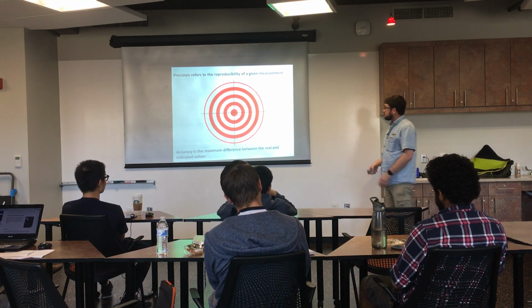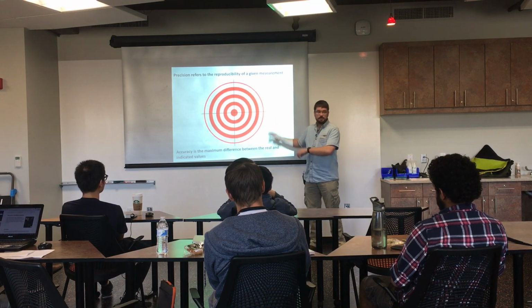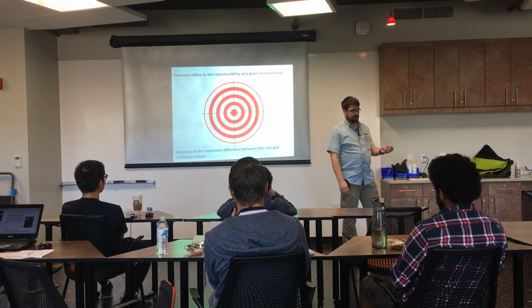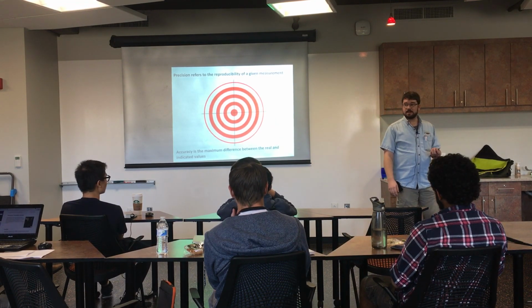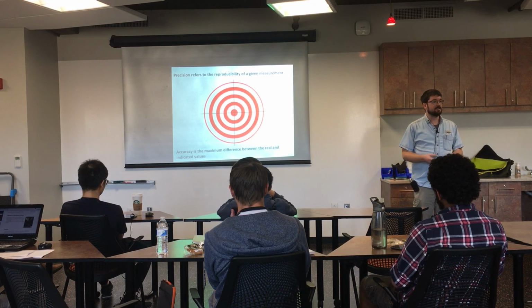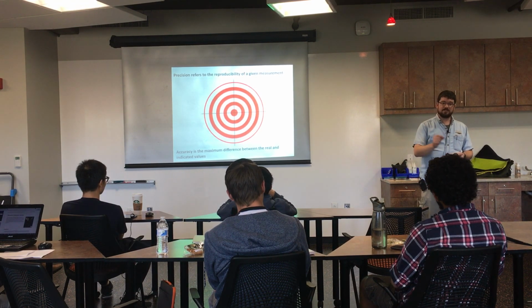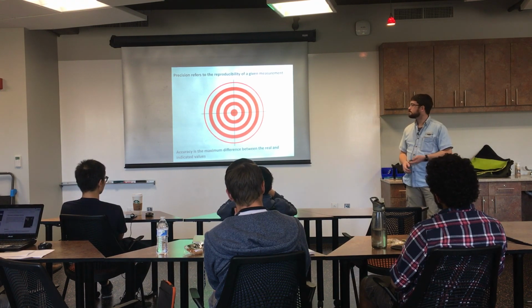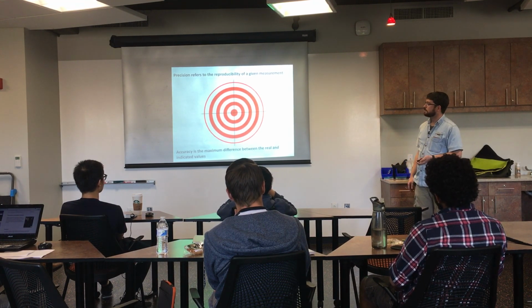Okay. So make sure that you look at these specs for the transducers, how reproducible the measurement is, and how close it's going to be to the actual physical value that you're trying to measure. A lot of times we don't necessarily care how close it is to the actual physical value. Maybe we want just relative changes. We really care about how precise it is, maybe not how accurate it is. It depends on the situation and what you're doing.